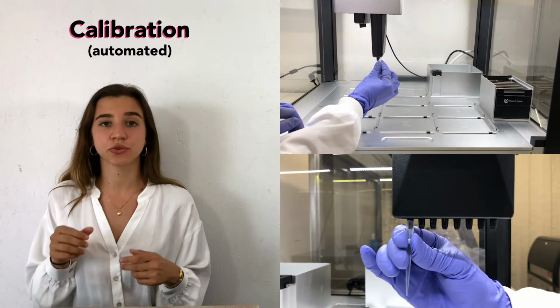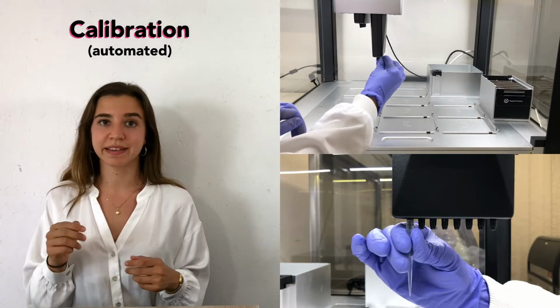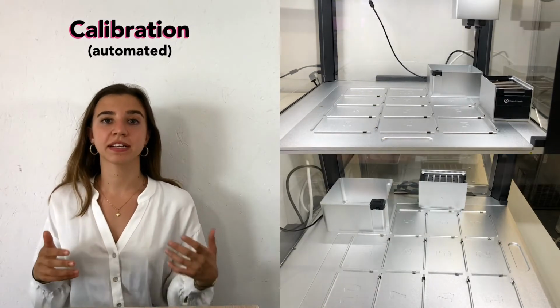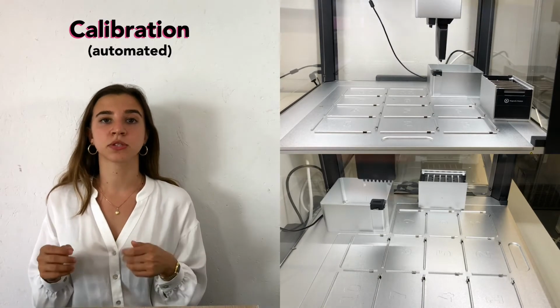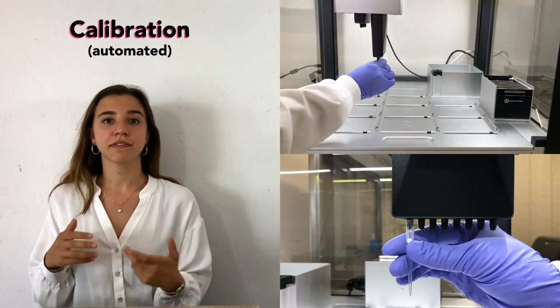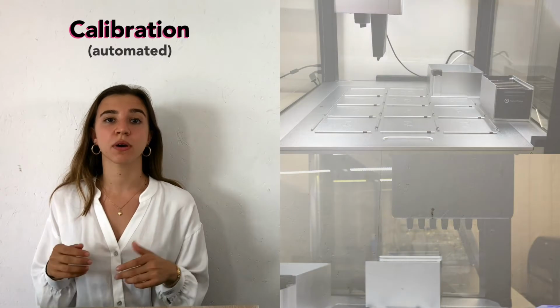Make sure to do this straight and from below and with a twist at the end. Now the OT-2 will calibrate itself through a series of sensor taps on the deck. The only thing left to do at this stage is remove the tip from the pipette.